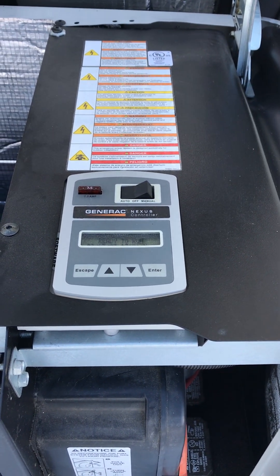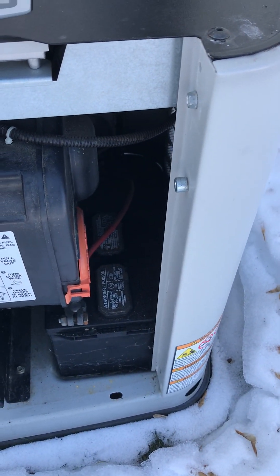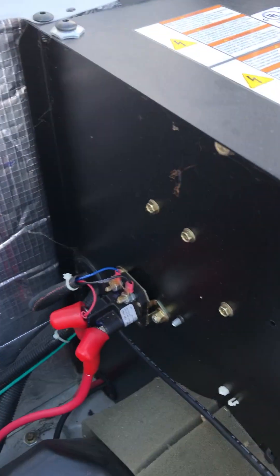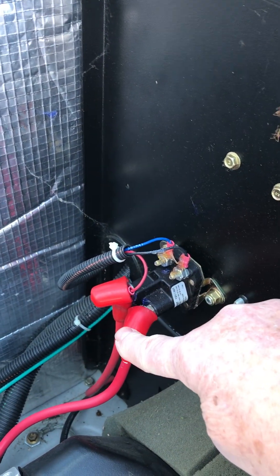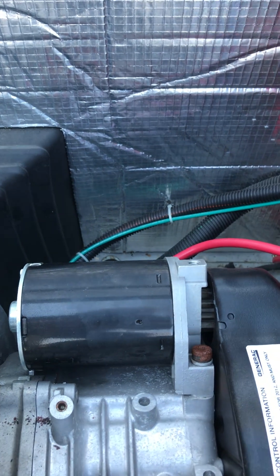The first thing I looked at was the battery, because those are really inexpensive and all they do is send a command to start, like turning the key in your car. The battery has to be in good condition, and it'll send 12 volts over to the starter relay, which connects these two posts here and allows current to flow to the starter.